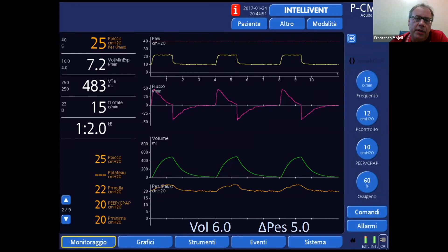And if you exceed with the filling volume, sometimes you can also see a decrease of pressure transmission, like in this case. So with 6 ml, the delta Pes decreased from 7 to 5 centimeters of water. So in this specific condition and patient, the optimal filling volume was 2 ml, because this was the lowest volume associated with the largest tidal increase of esophageal pressure.